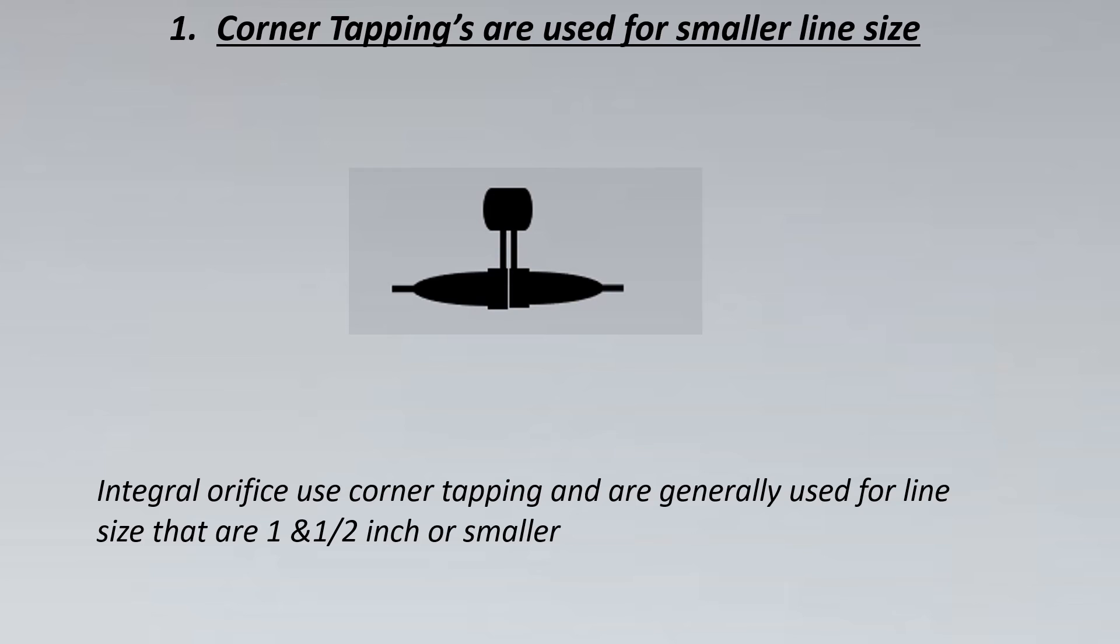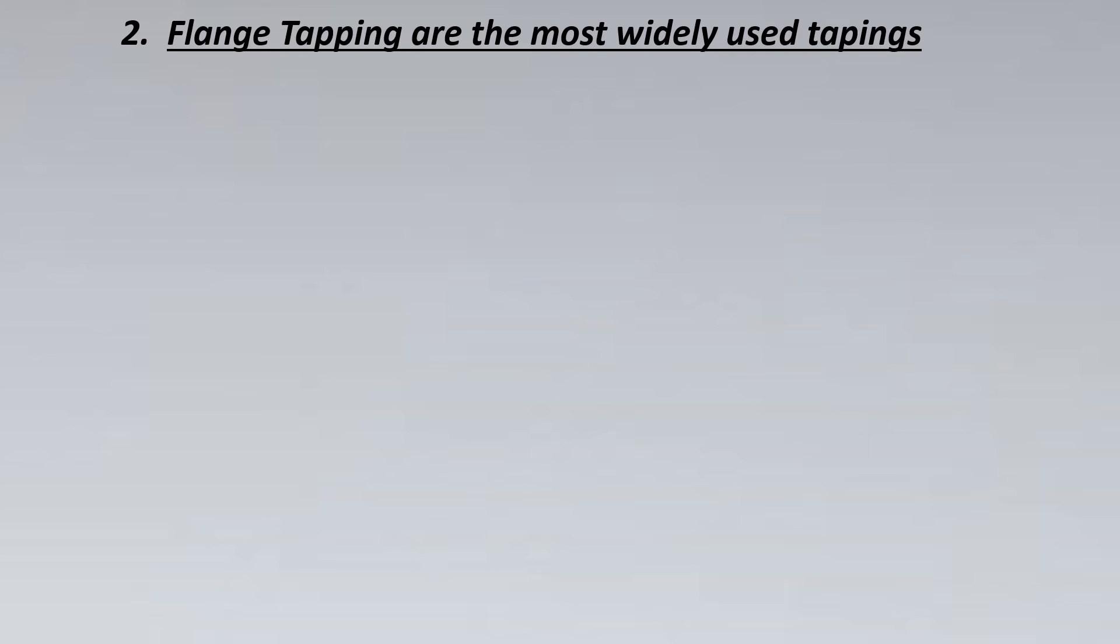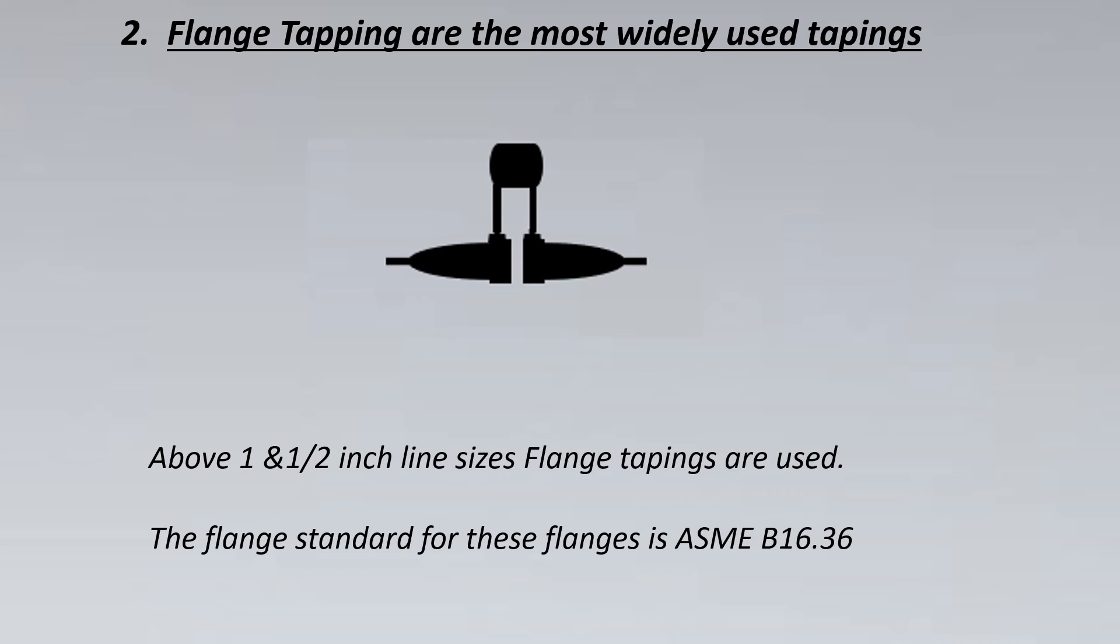Now let's look into the flange tappings. These are one of the most widely used tappings. Sometimes it's the piping department who provides us this kind of flanges having the drills inside them, or we can also take it from the instrument vendor. These are usually used for one and a half inch line sizes and above. And the flange standard, yes that's a good one, it's ASME B16.36.